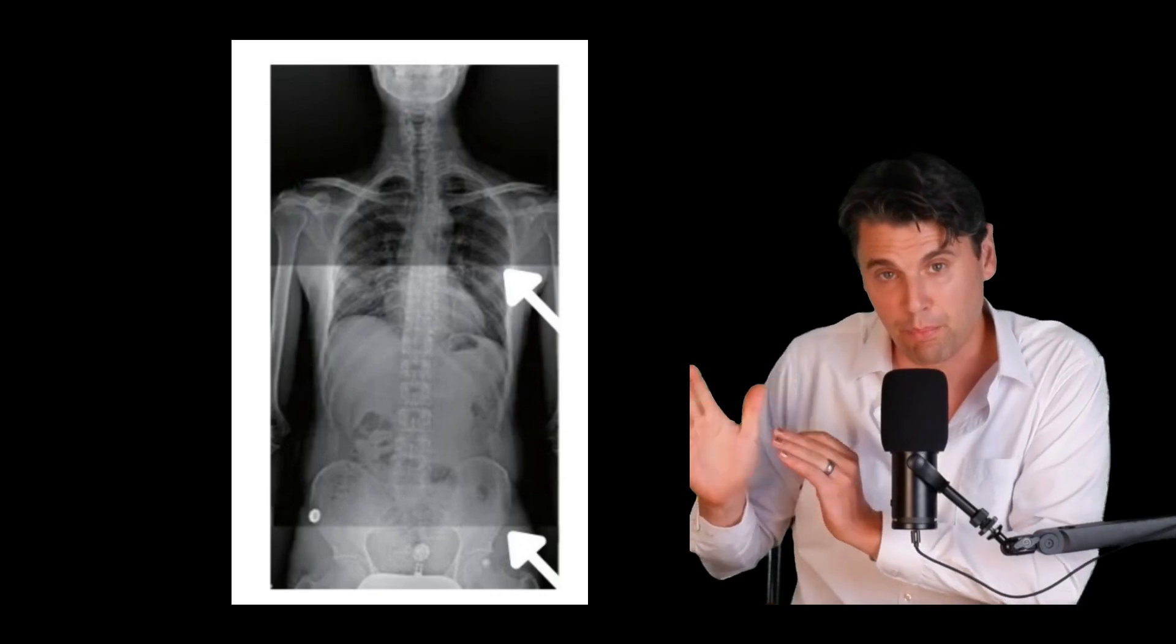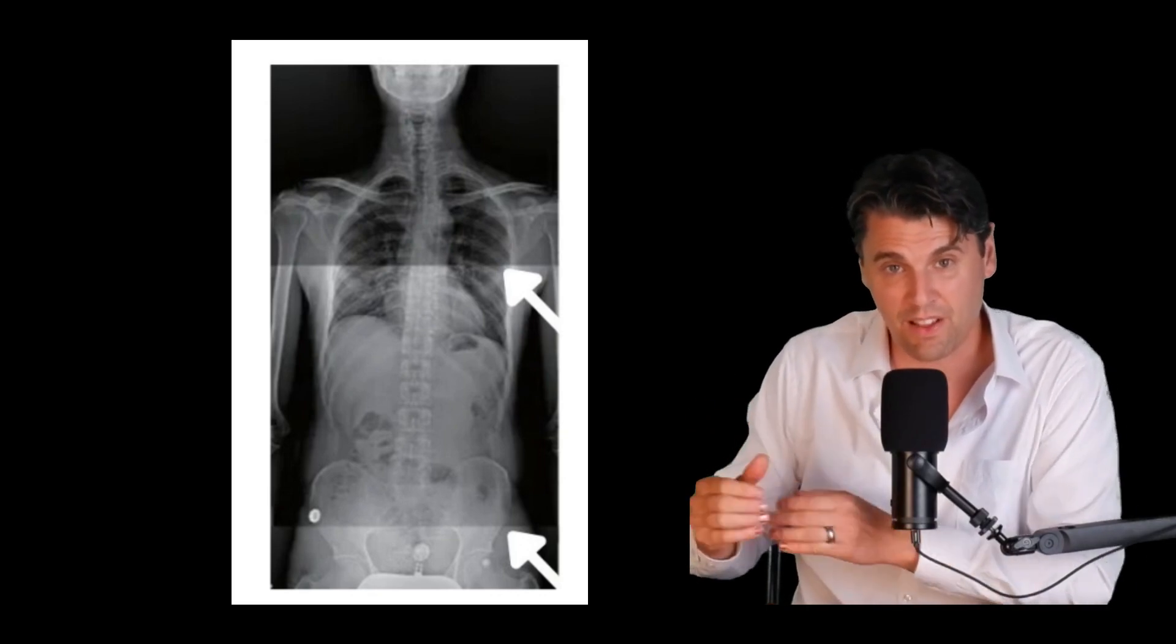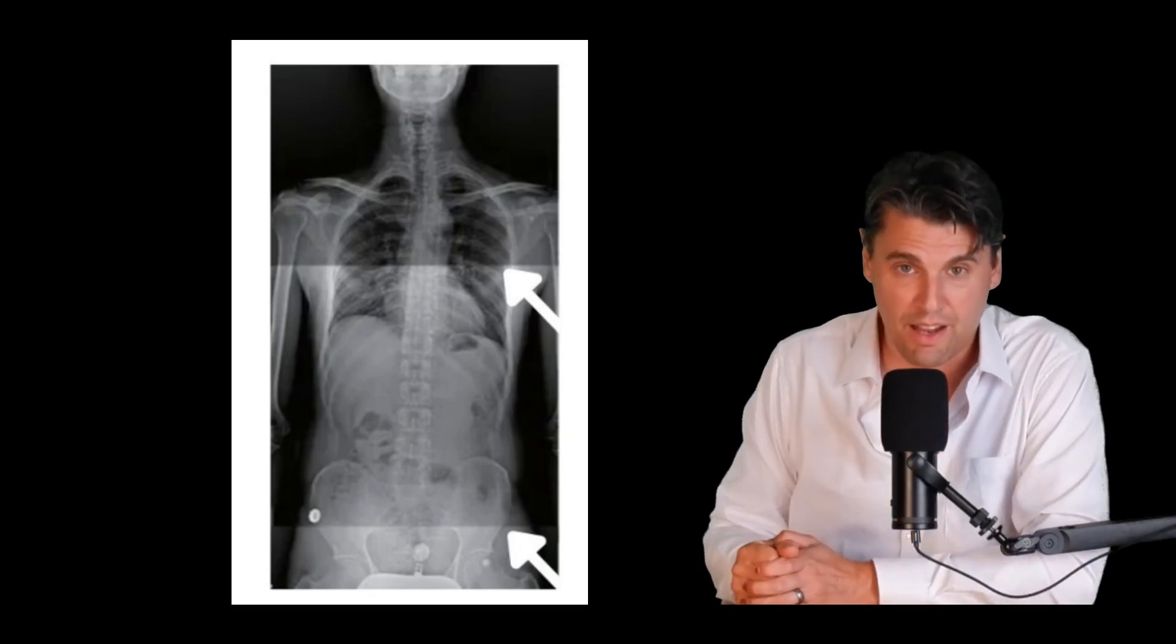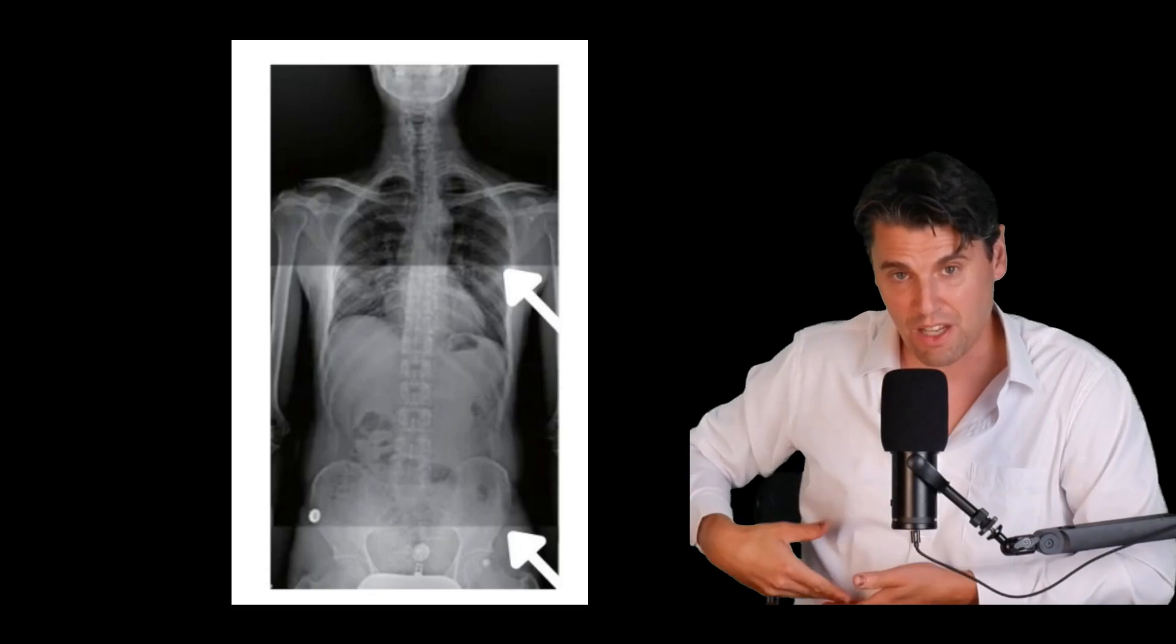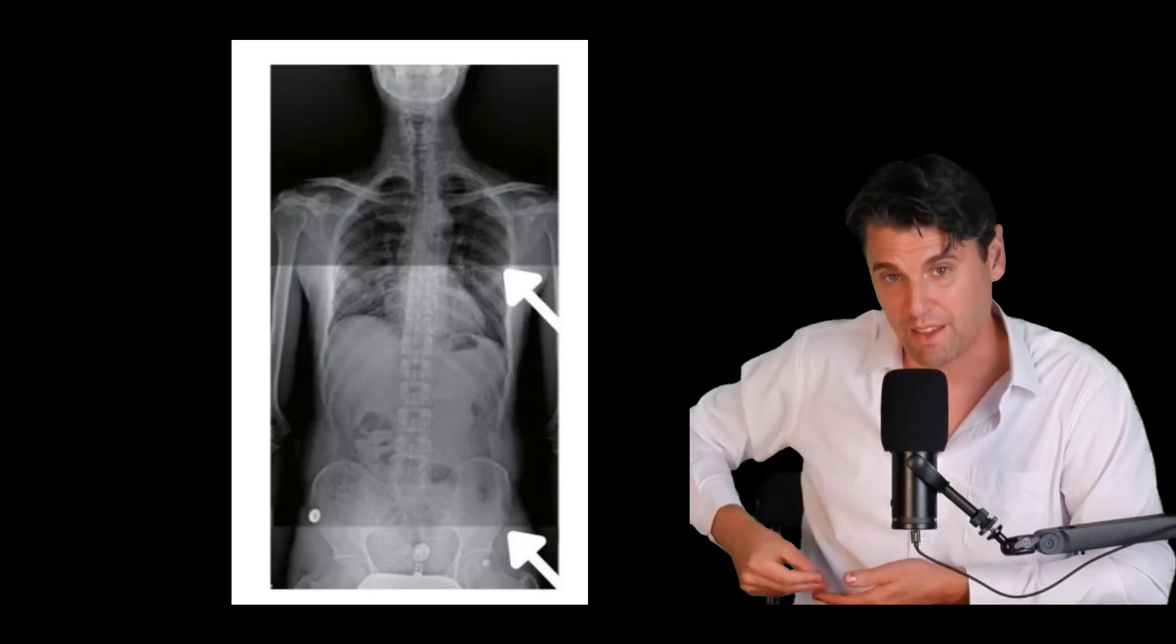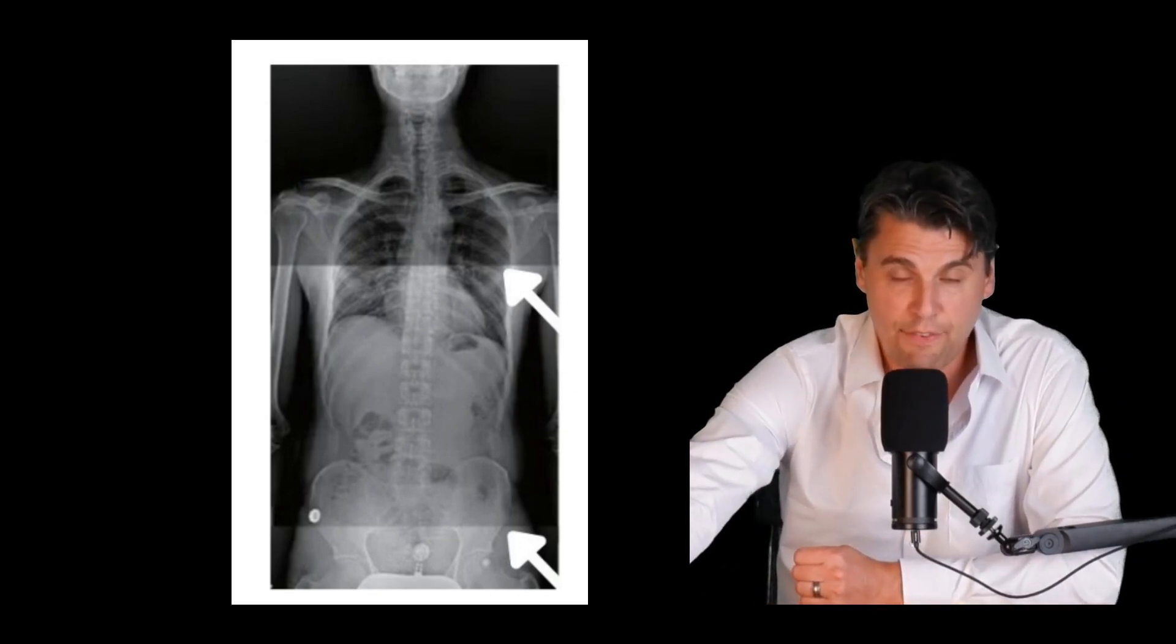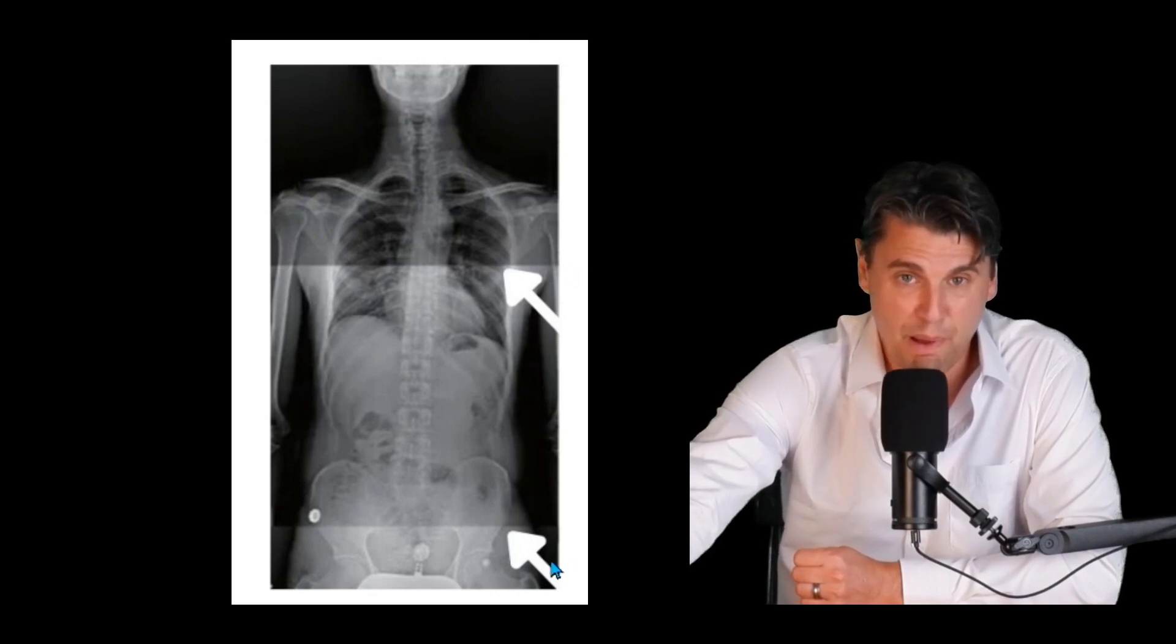We call that beam hardening and specifically the heel effect because you're actually going to have a different energy on either what we call the heel side or the non-heel side. These kinds of things can lead to differences in your attenuation such that you can see at the boundary there's a seam.